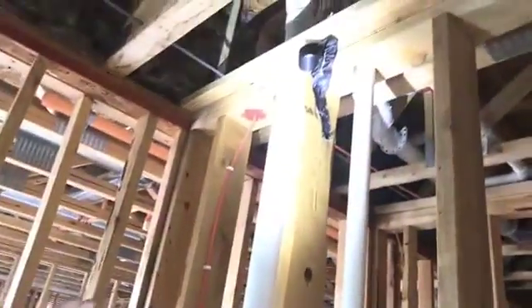Again, checking here. All these penetrations going up, including the dryer exhaust, have been sealed in the top plate so that we're not going to have this air leakage into this envelope at the ceiling level. And here they've got to do a few they've missed. There hasn't been a formal framing inspection on this floor yet. That is going to be next. You can see they've already started caulking some of the framing members.